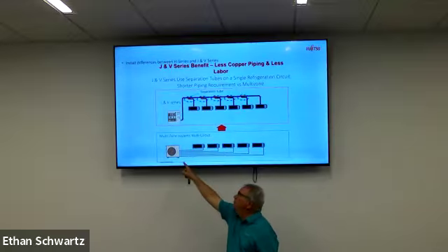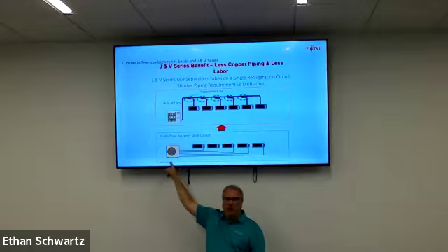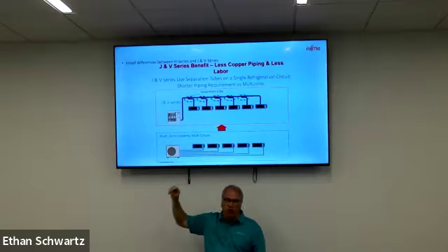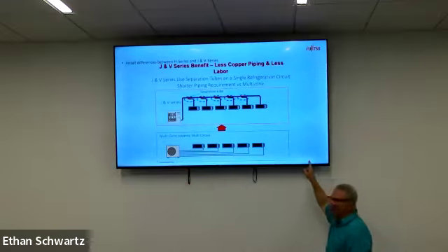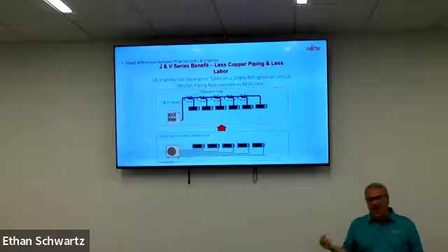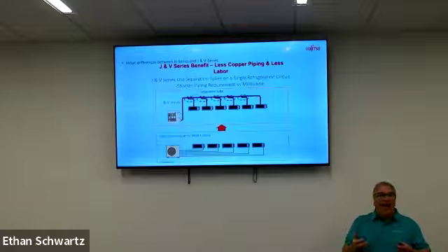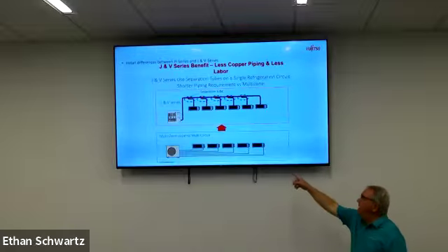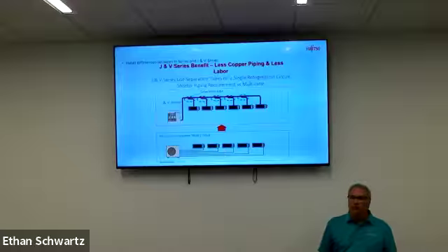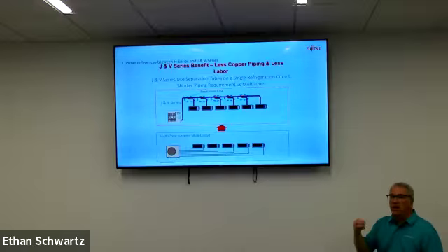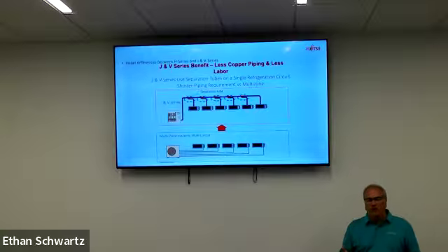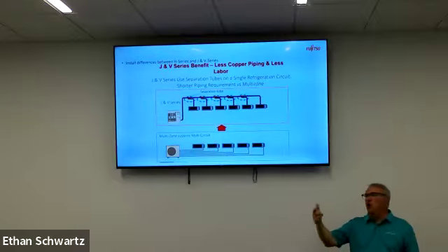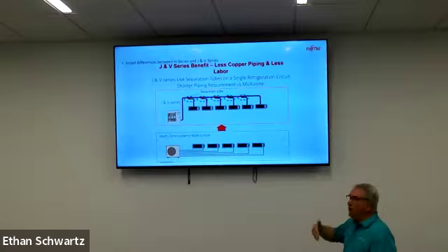mini split, because once we're past that electronic expansion valve in that outdoor unit, now we are a subcooled liquid line, and the length of that can cause a change of state in the refrigerant because of pressure drop. And if we start to do that, when we get to the actual indoor unit, we lose our net refrigerating effect. We're losing the cooling ability, because the maximum amount of BTU absorption with a refrigerant is when it changes state, when it goes from liquid to gas or gas back to liquid. That's the most number of BTUs.